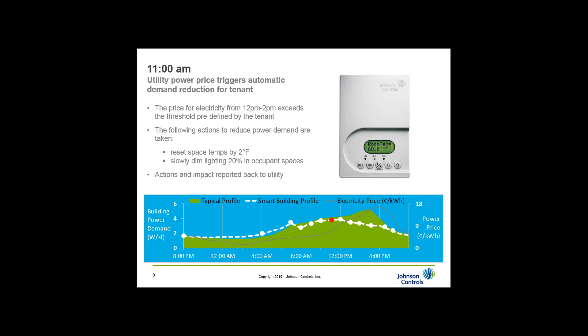12 p.m. comes around, and the power price triggers an automatic demand reduction for the building owner, so they're able to start either dispatching ice storage for the cooling if needed, the chilled water set points on the chillers are increased, and then the lighting controls come into place. And all these actions and their effects are reported back to the utility so that the owner can be compensated for those demand avoidances.